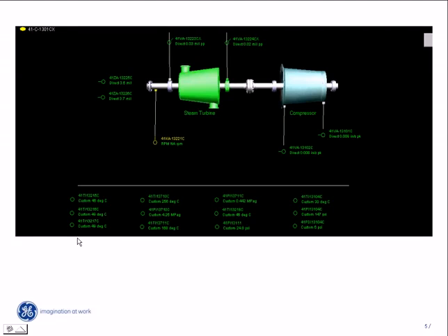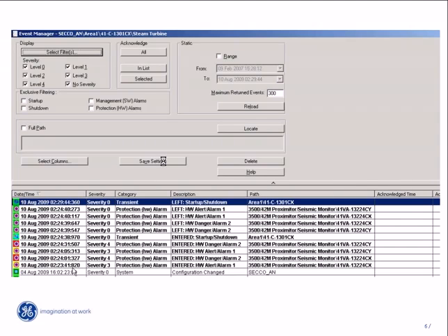The on-duty staff quickly connected to the system. From the message received, it was easy to find the problem machine in this large facility. The machine had already stopped. This is probably due to the protection system tripping on high vibration. Quickly checking the event manager, it was clear to see the order in which the alarms had occurred. Severity 3 at 2:23 on the X probe, and then severity 4, severity 3 on the Y probe, severity 4 on the Y probe, and then machine shut down.